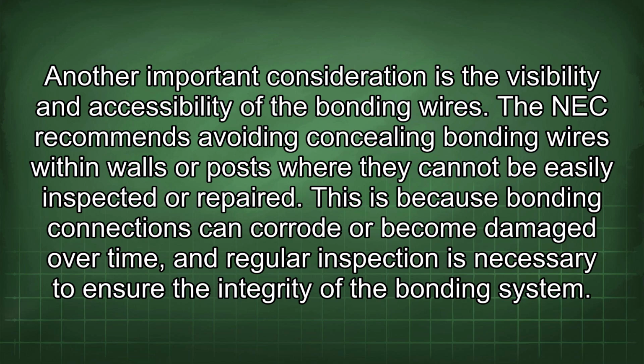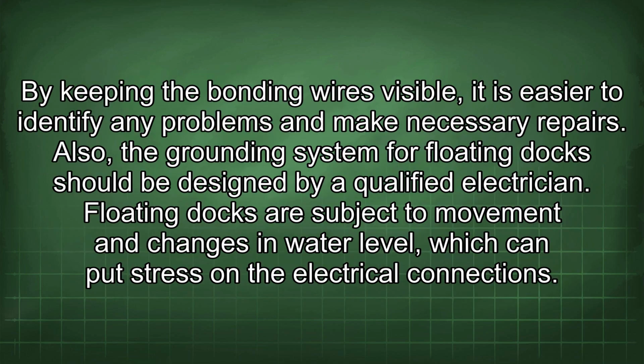Another important consideration is the visibility and accessibility of the bonding wires. The NEC recommends avoiding concealing bonding wires within walls or posts where they cannot be easily inspected or repaired. This is because bonding connections can corrode or become damaged over time, and regular inspection is necessary to ensure the integrity of the bonding system. By keeping the bonding wires visible, it is easier to identify any problems and make necessary repairs. Also, the grounding system for floating docks should be designed by a qualified electrician.